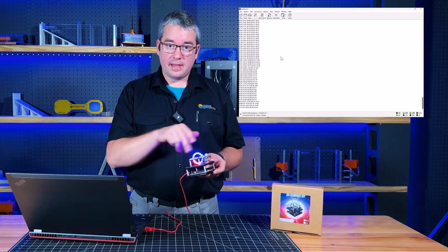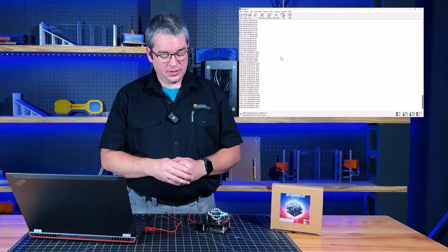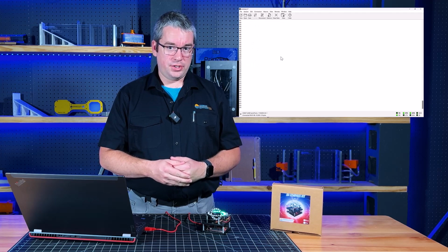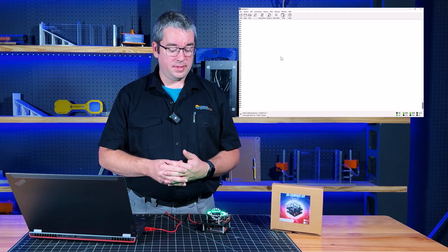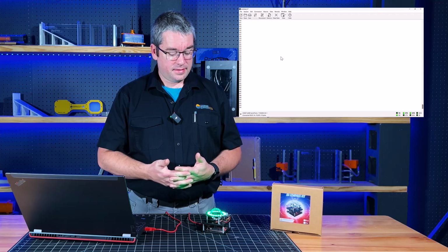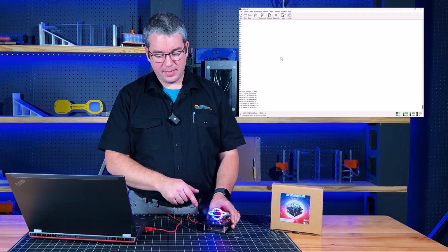Or during the calibration phase of the instrument, you can just leave it stationary and it's not going to get any good calibration data. So what we're going to see is the output's going to be a little more jittery on the lights. And then, see, it's jumping around quite a bit.